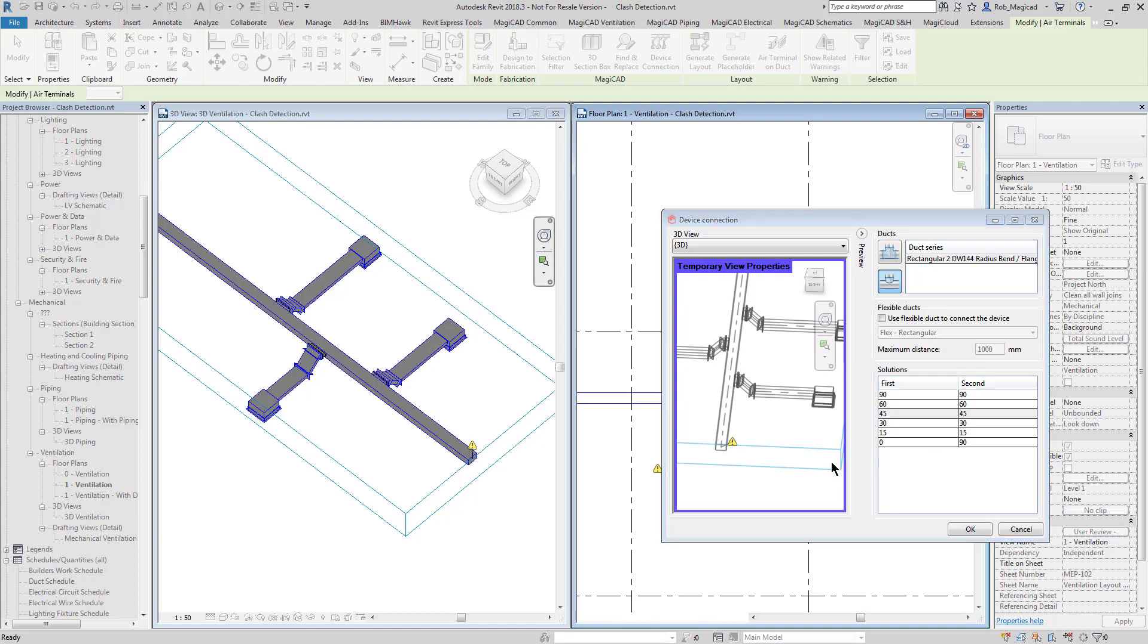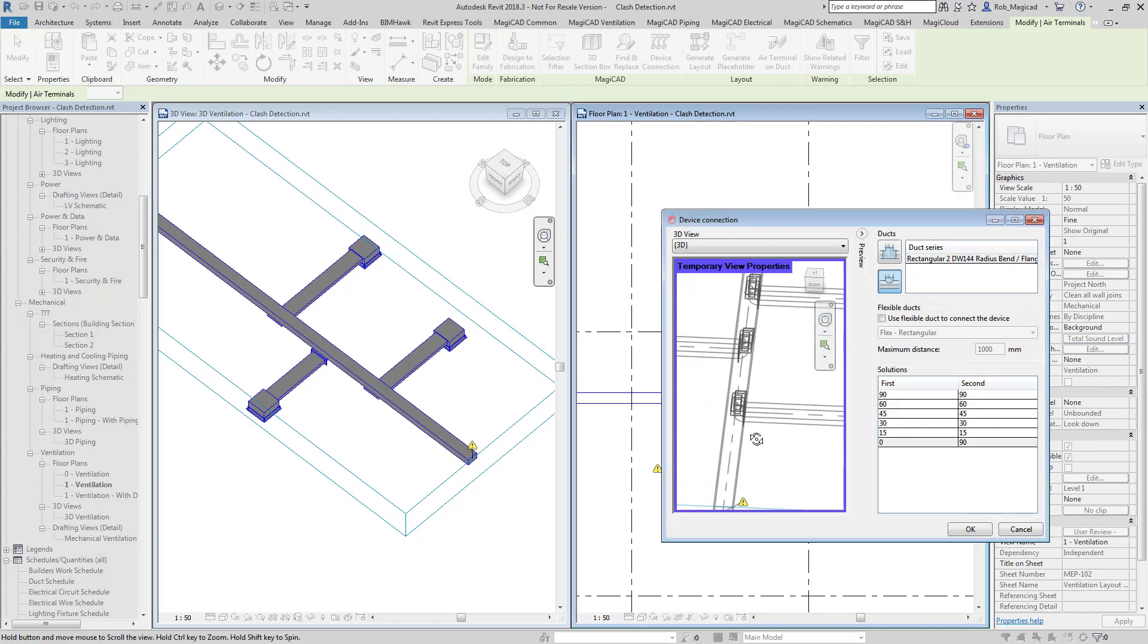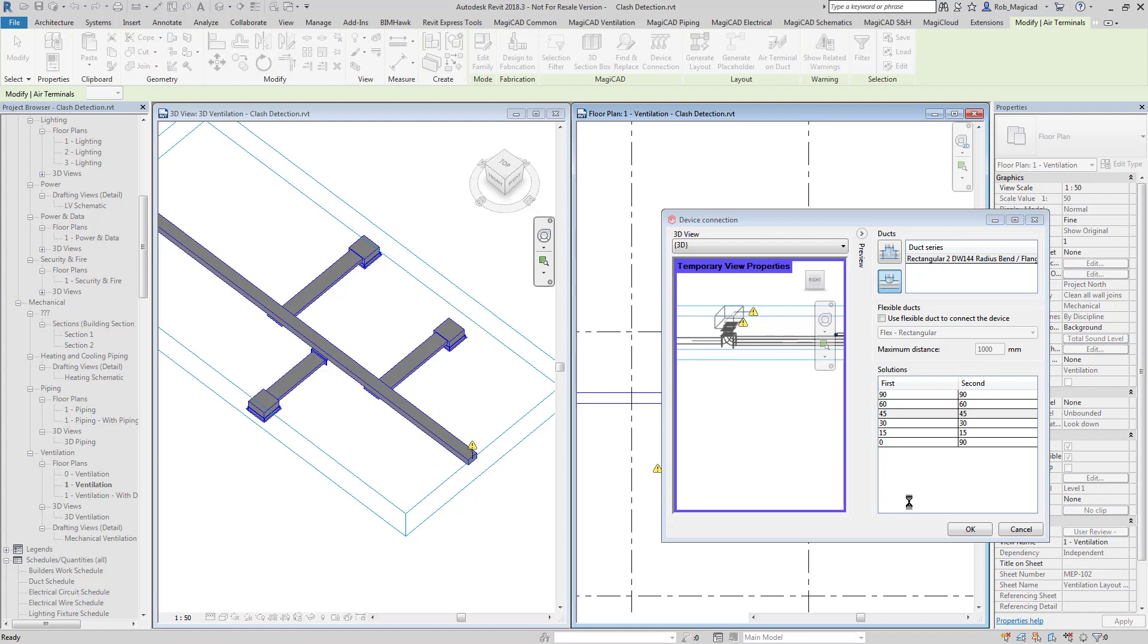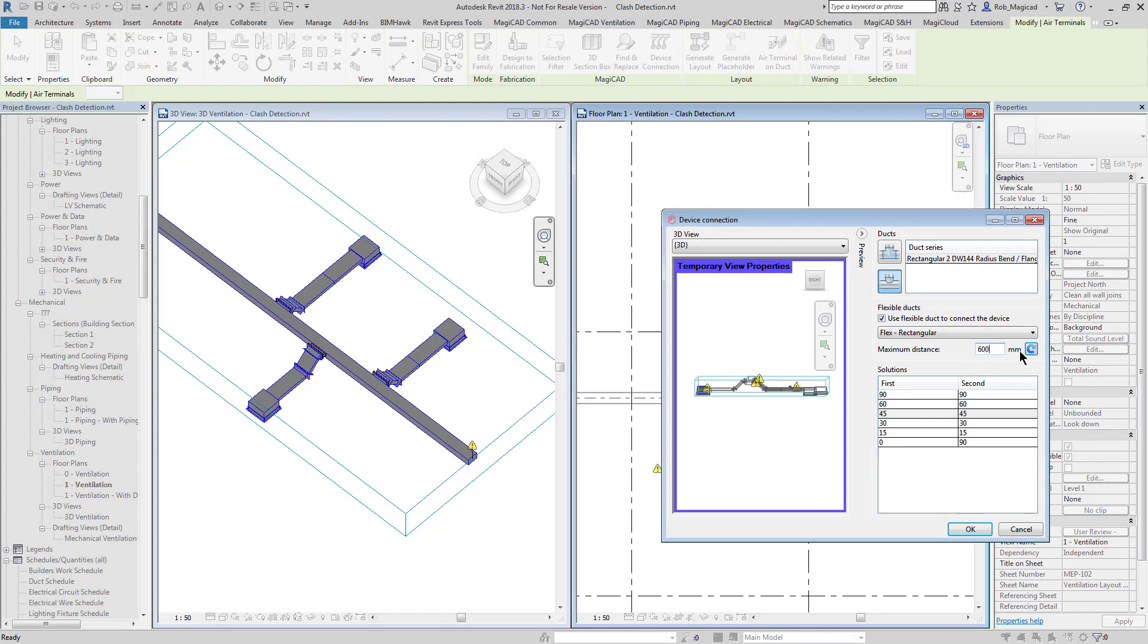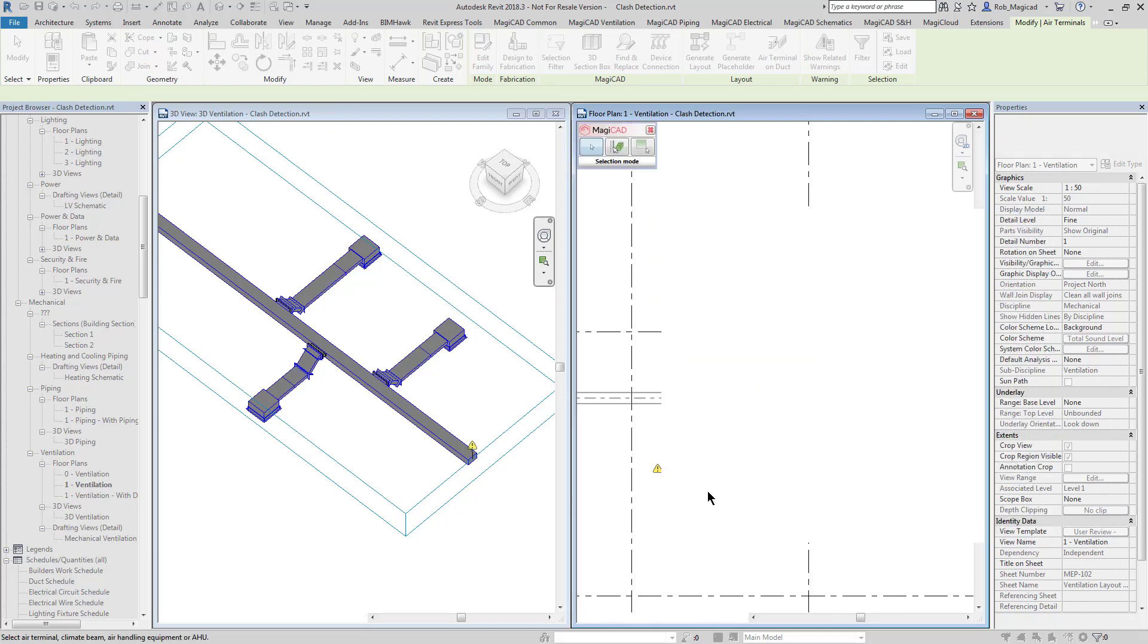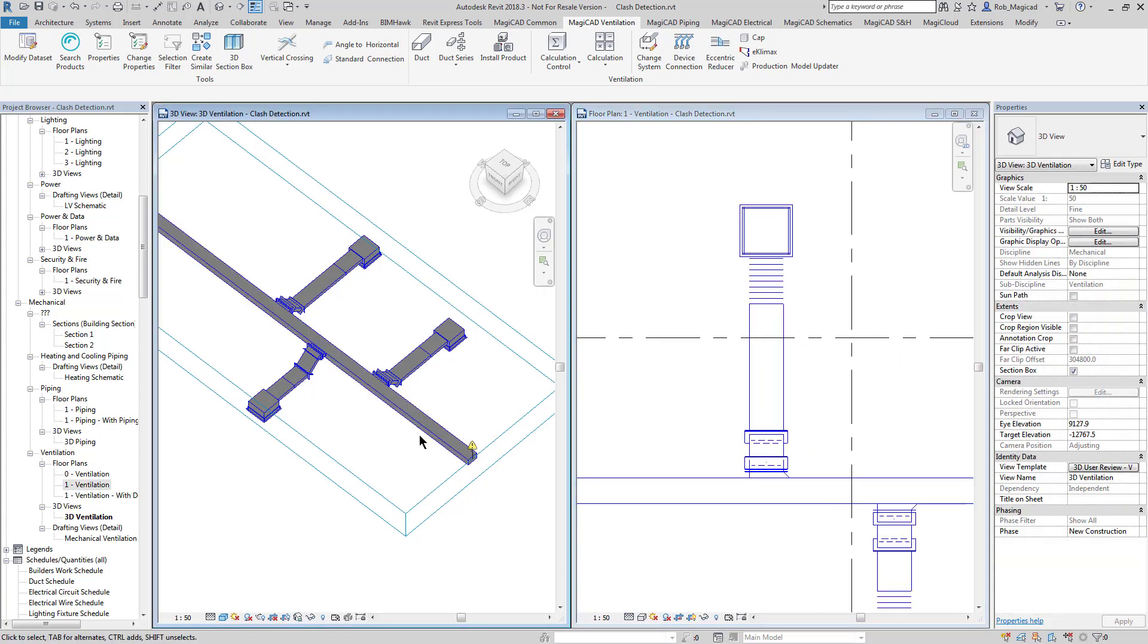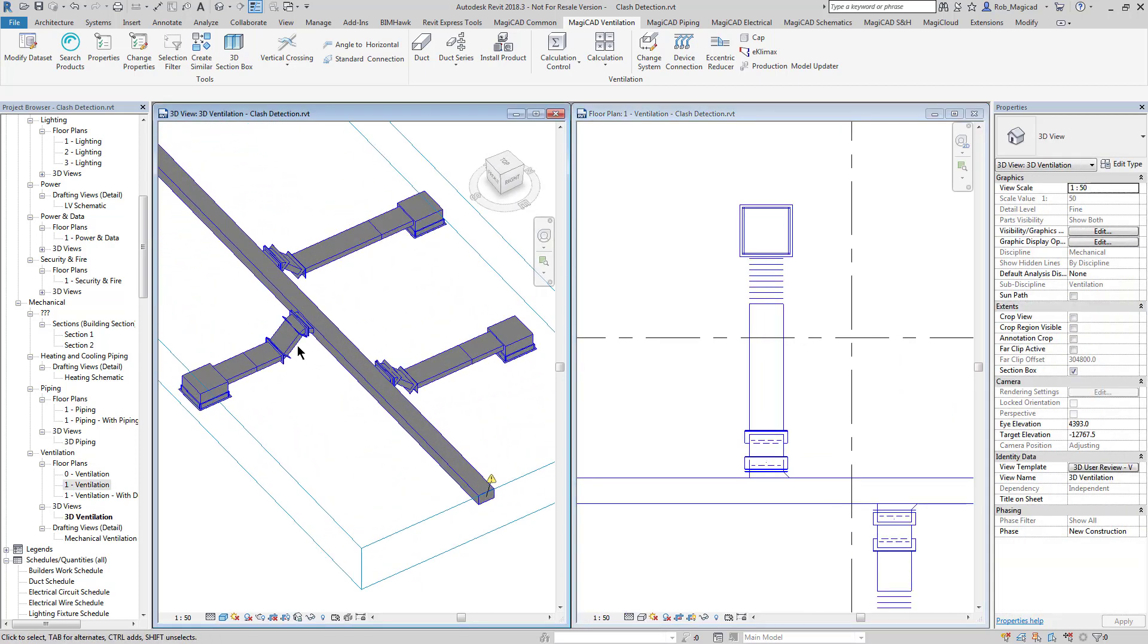The other option is you can actually come straight off the bottom if you want to do that as well and just go straight in. But I think I want to come off the side at two 45-degree angles, so I'm going to go with that. And like normal, you want to choose flexible ductwork at the end. You can choose this and then choose a length that's suitable, let's say 600, and you can add the flexible rectangular ductwork to the end of that as well. Then press OK, and there's the solution. It's now put the grills connected to the ducts with the flexible connection as you see fit.